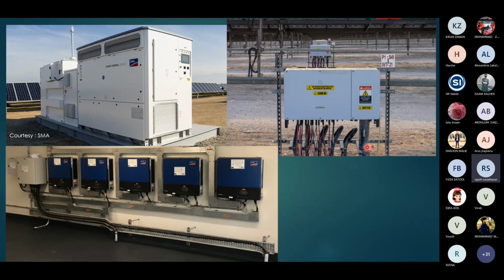I would not say completely standard, because the protection settings and the transmission are slightly different to the conventional power plants, because for the transformers, the neutral, the star point is not earth. We keep it floating for a particular reason. We have floating IT type of transformers in large scale string inverter based applications.